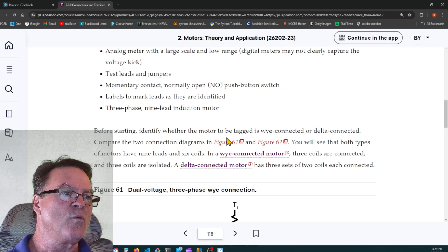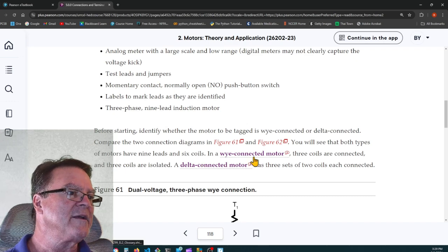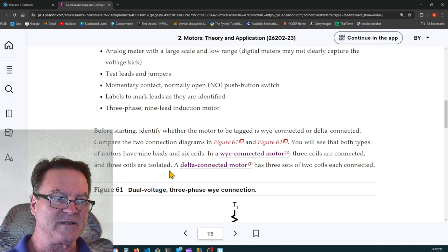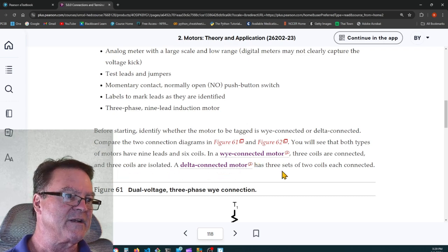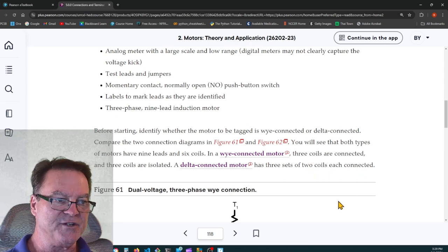Before starting, identify whether the motor to be tagged is Y-connected or delta-connected. Compare the two connection diagrams, figures 61 and 62. You'll see that both types of motors have 9 leads and 6 coils. If a Y-connected motor, 3 coils are connected and 3 coils are isolated. A delta-connected motor has 3 sets of 2 coils, each connected.